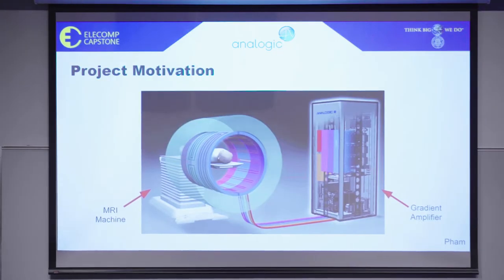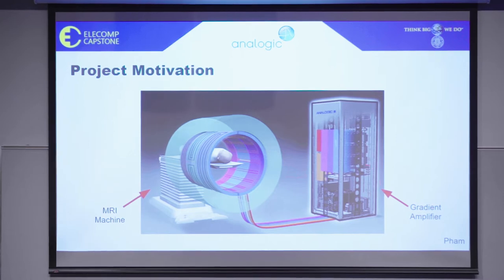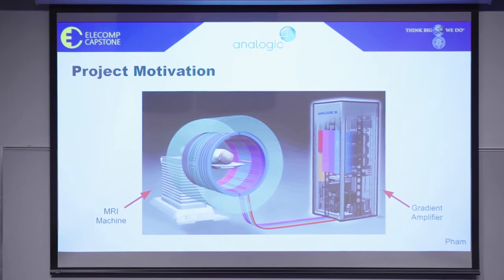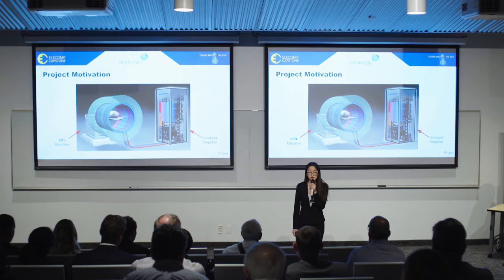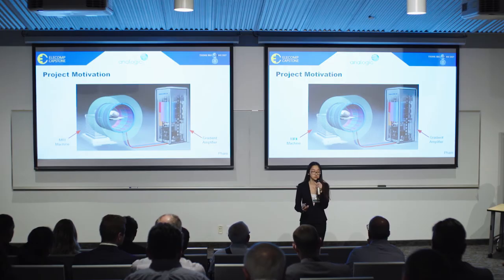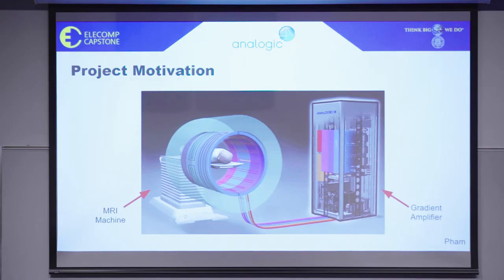The motivation for our project comes from the gradient amplifiers which Analogic provides for use in MRI machines. To get good MRI results and high-resolution images, it is crucial to have variable magnetic fields, high power, wide bandwidth, and low noise. This is exactly what the gradient amplifier provides.